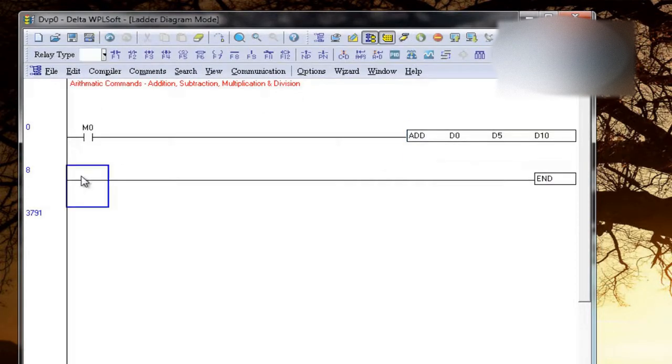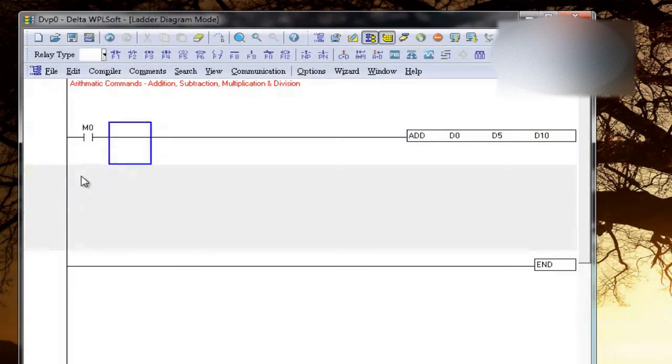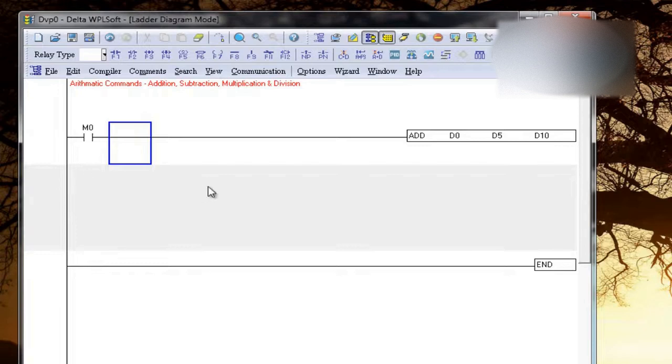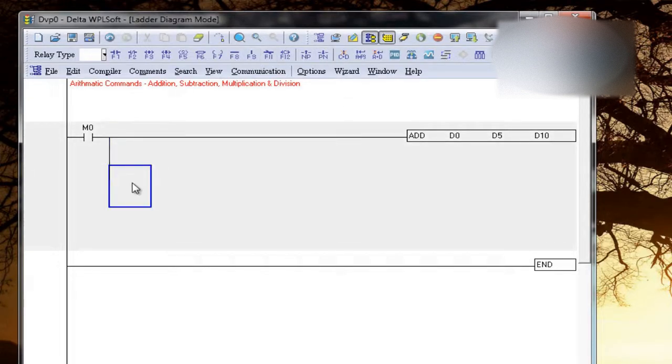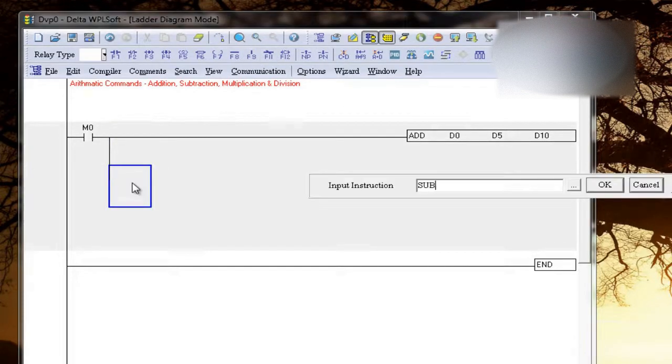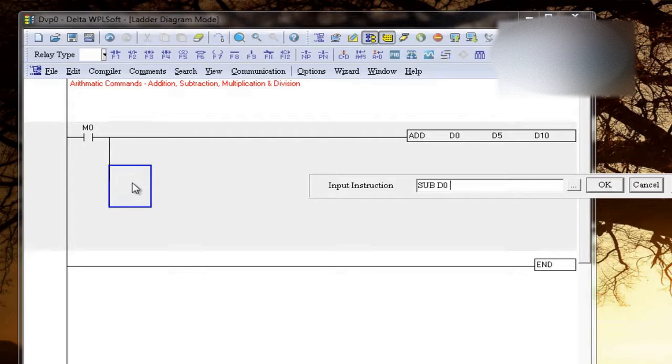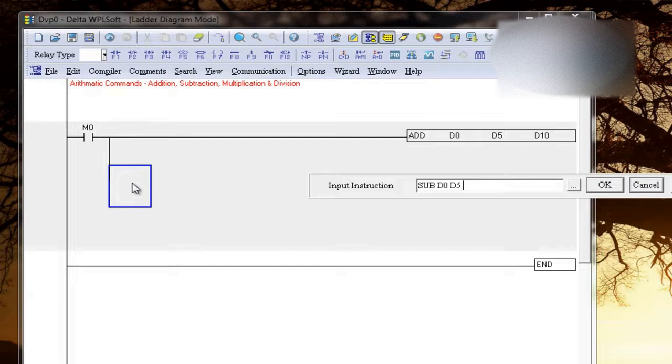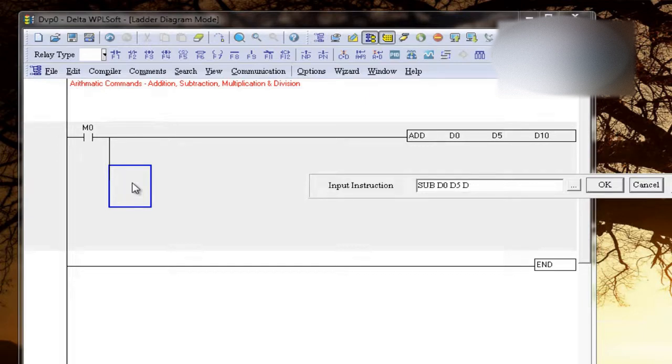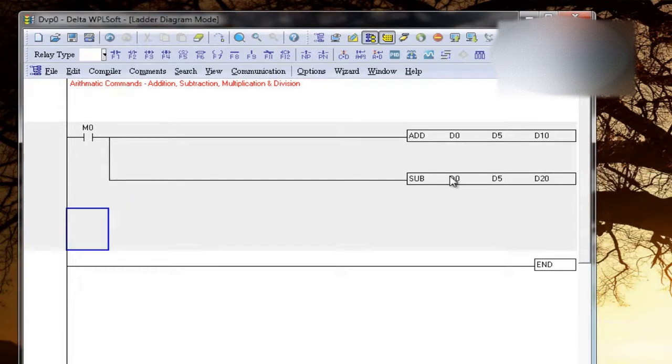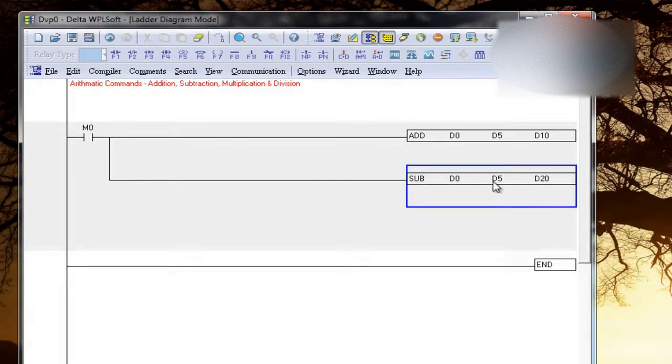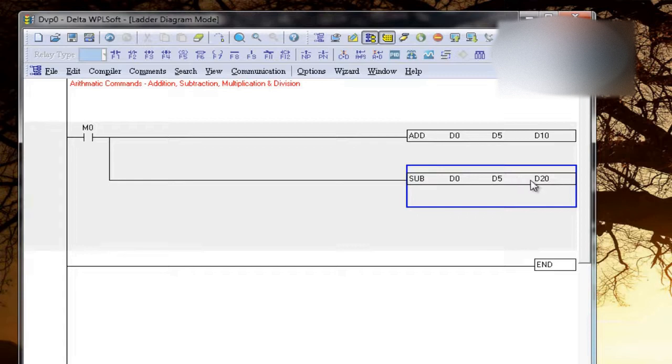So parallelly we can also use subtraction. I can write in parallel of this M0. For subtraction I will write SUB, now D0, D5, sorry, D5 and store the result in D20. So it will subtract D0, subtract D5 from D0, so it's D0 minus D5 and the result will be D20.